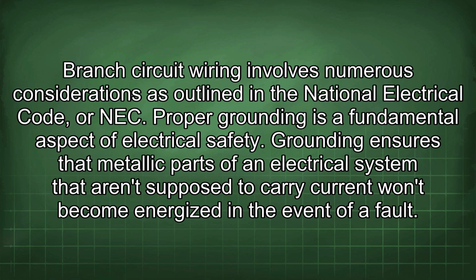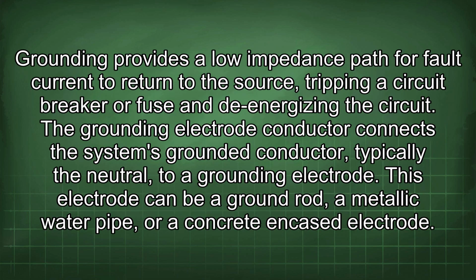Branch circuit wiring involves numerous considerations as outlined in the National Electrical Code, or NEC. Proper grounding is a fundamental aspect of electrical safety. Grounding ensures that metallic parts of an electrical system that aren't supposed to carry current won't become energized in the event of a fault. Grounding provides a low impedance path for fault current to return to the source, tripping a circuit breaker or fuse and de-energizing the circuit. The grounding electrode conductor connects the system's grounded conductor, typically the neutral, to a grounding electrode. This electrode can be a ground rod, a metallic water pipe, or a concrete-encased electrode.